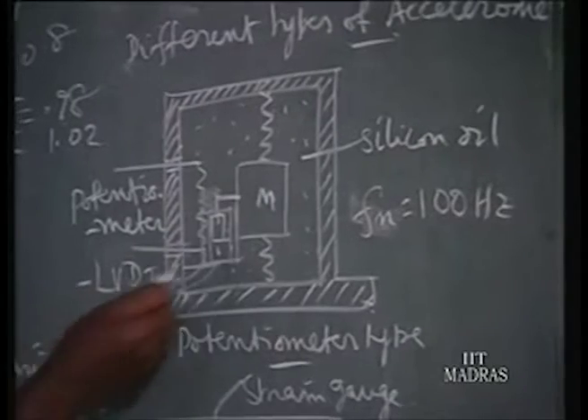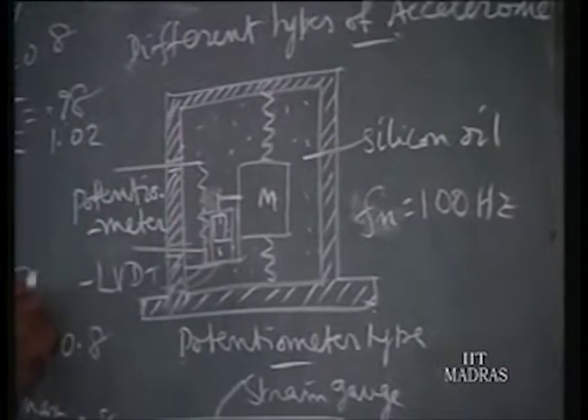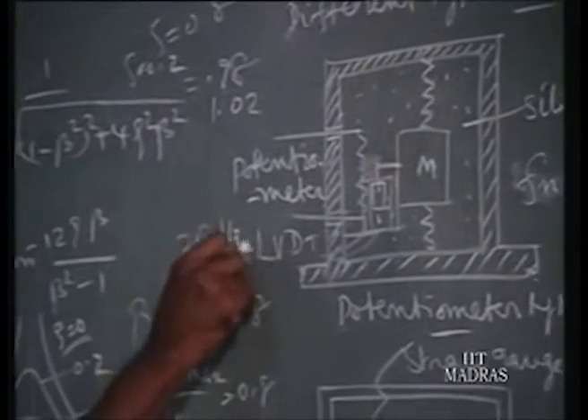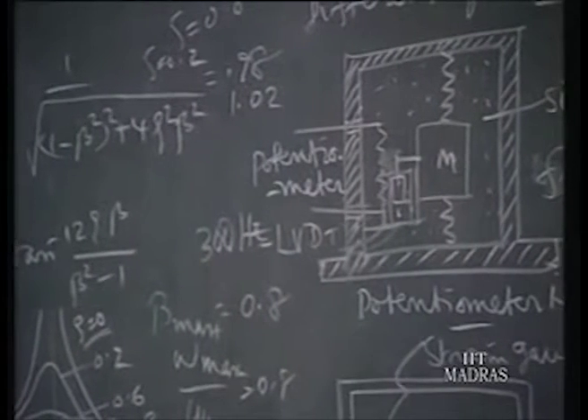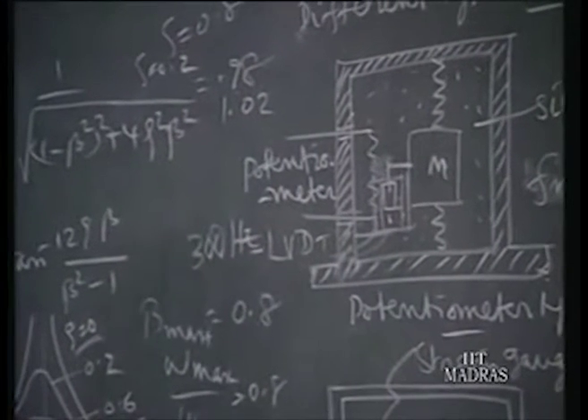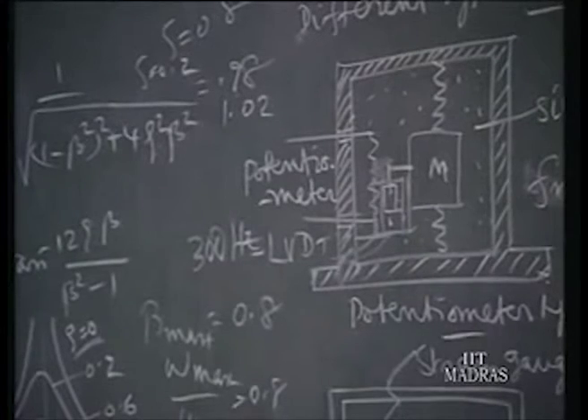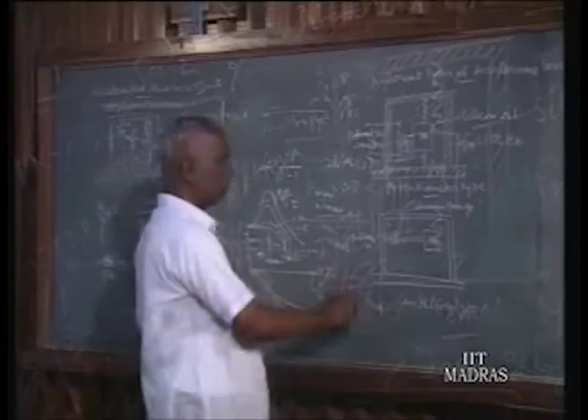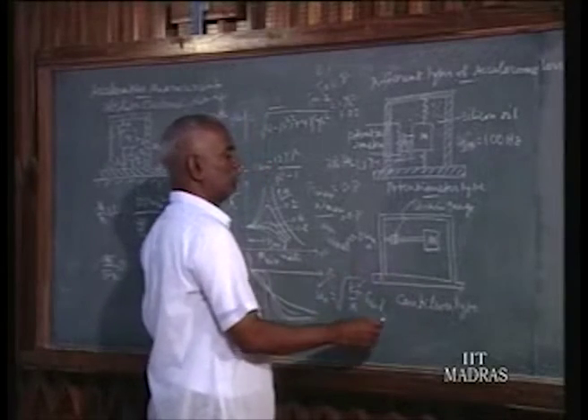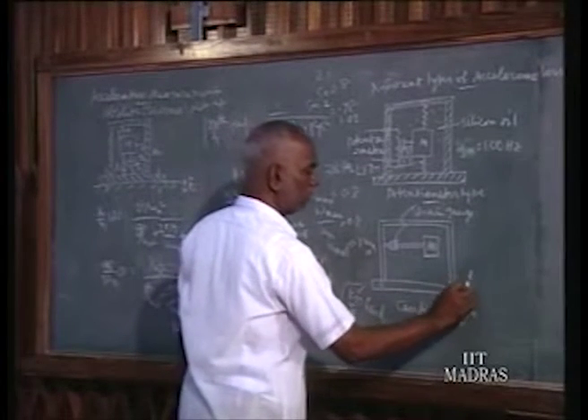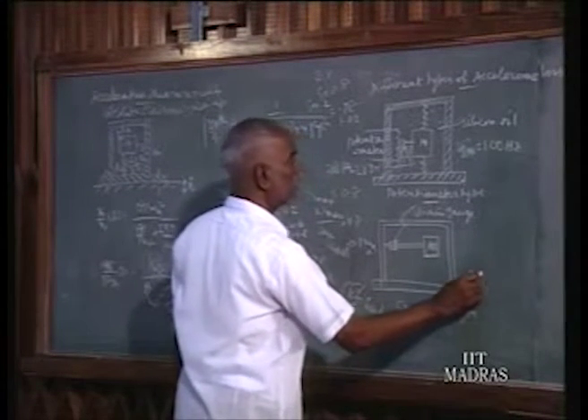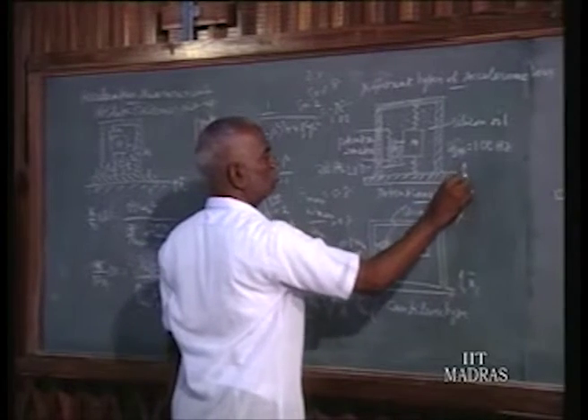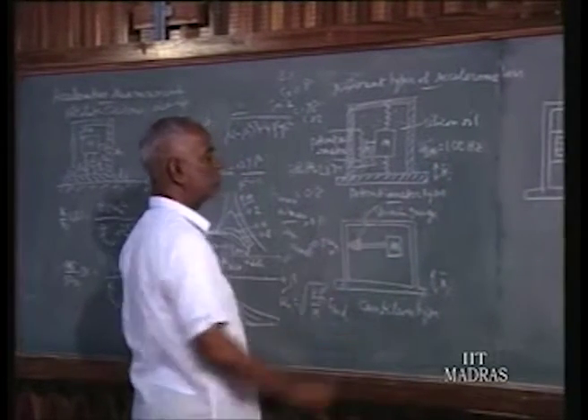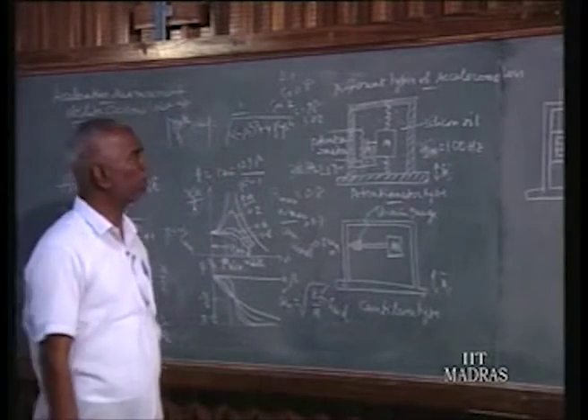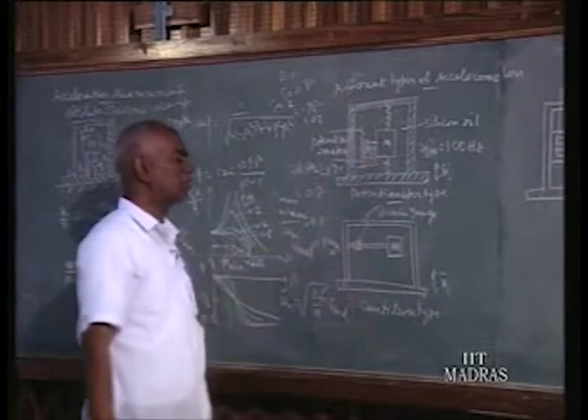If you use an LVDT, resistance for motion is small, then the omega n goes up to 300 Hz. Higher omega n means we have got higher bandwidth, that is an advantage. So another type is the cantilever type, and here the xi 2 dot measuring direction is this one. Here also it is this one. Xi 2 dot is the measurement direction. Always in the instrument, the accelerometer, they write the measurement direction.